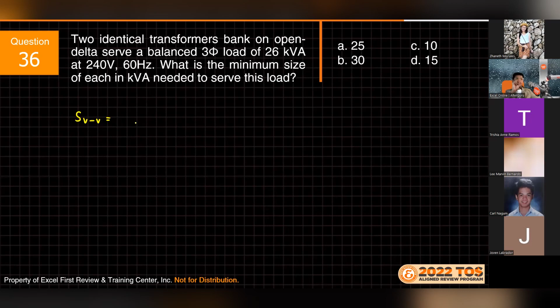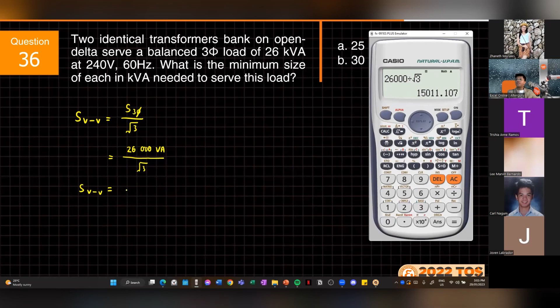Ibig sabihin, ano yung load doon? That's 26 kVA all over square root of 3. Ang S open delta becomes 26,000 over square root of 3, equals 15.011 kVA. So ganun lang siya i-compute.